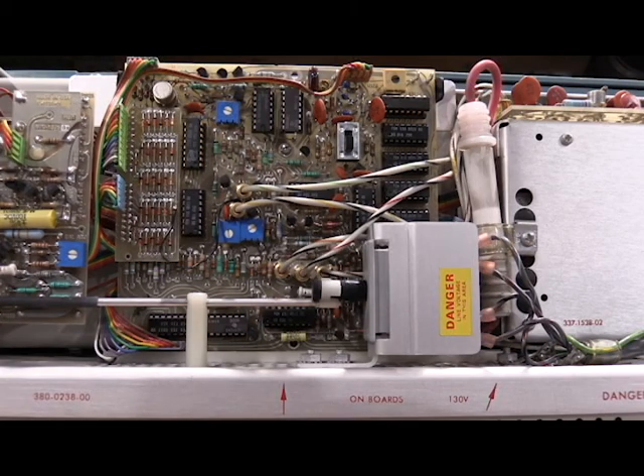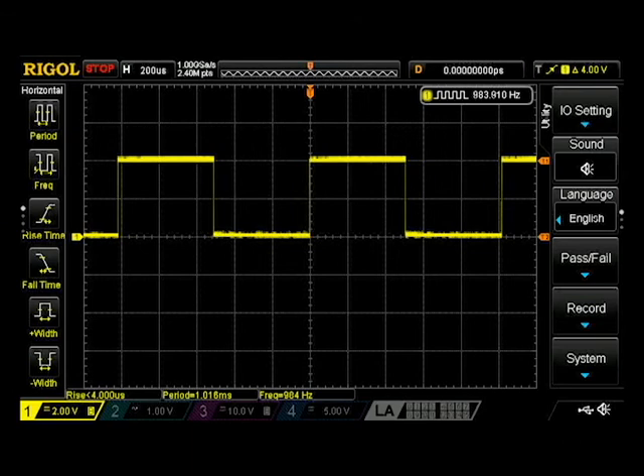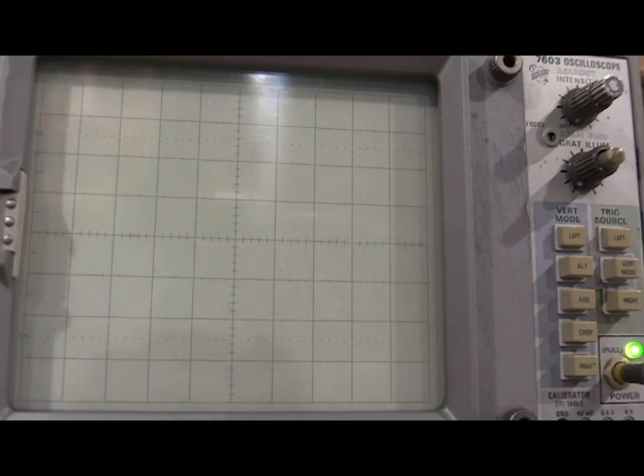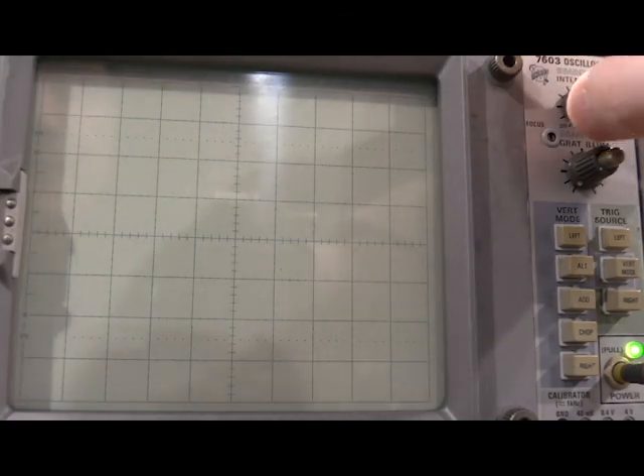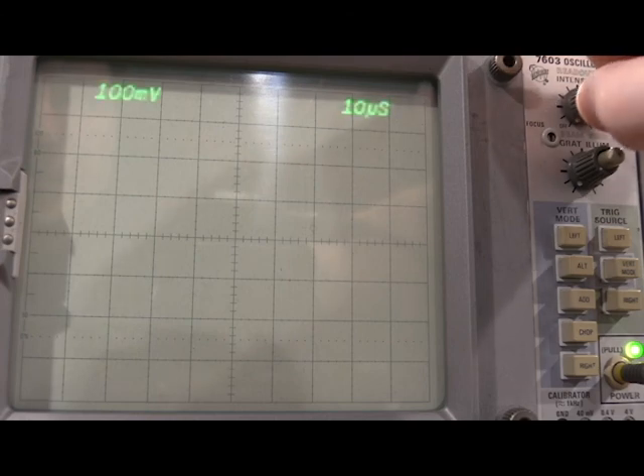So I've got to turn the scope back off and move that jumper back down so it's putting out the square wave it's supposed to. The last two steps in checking and calibrating these frames are checking the readout and the signal output on the back of the scope. The signal outputs are all good, everything's working there. I just wanted to show the readout, that everything was good there and it did not need to be adjusted.